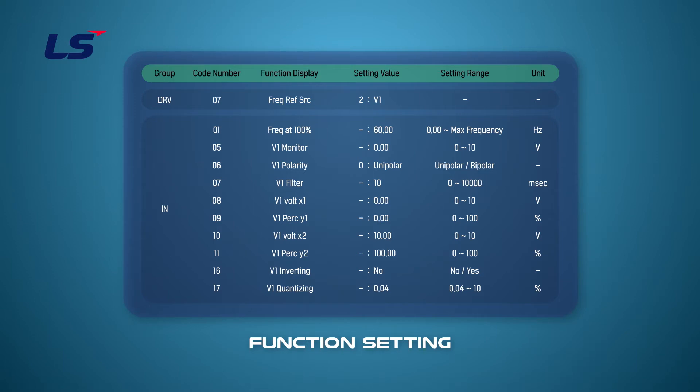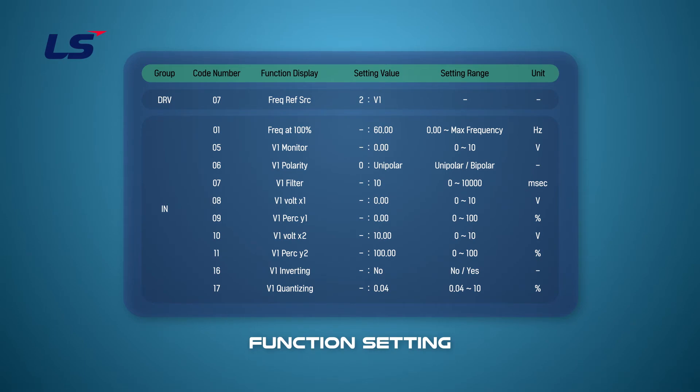Parameters related to analog input can be set in IN-group. First, set IN-group 6 to unipolar because we do not use the negative voltage now. If you want to use minus 10 volts to plus 10 volts, you can set bipolar.